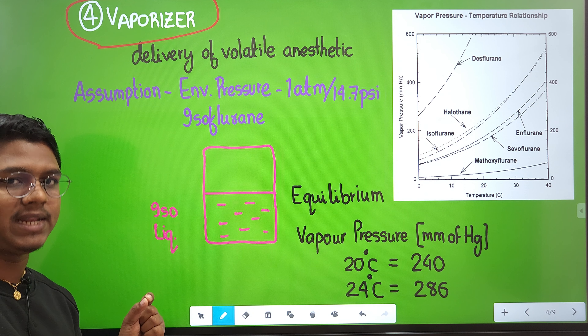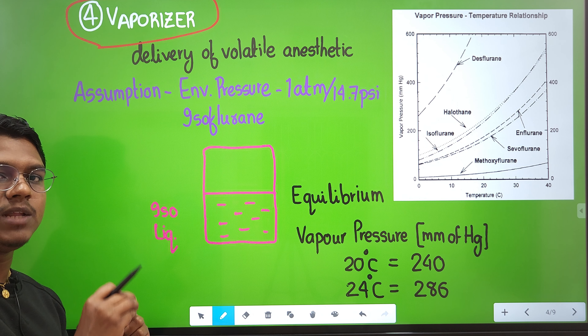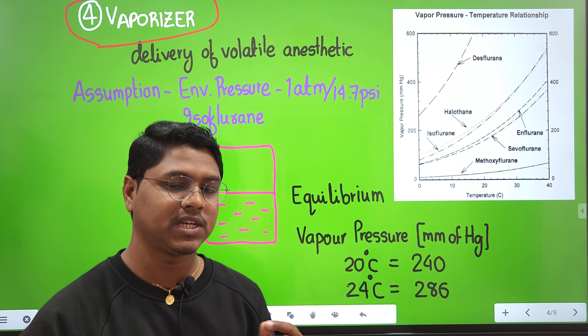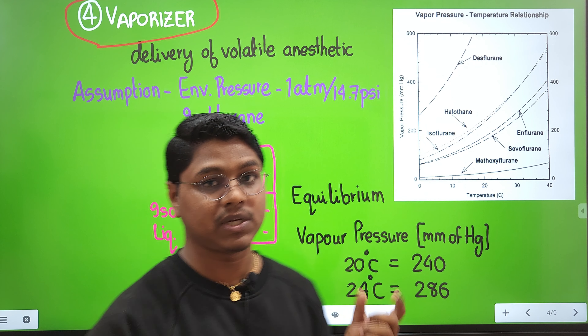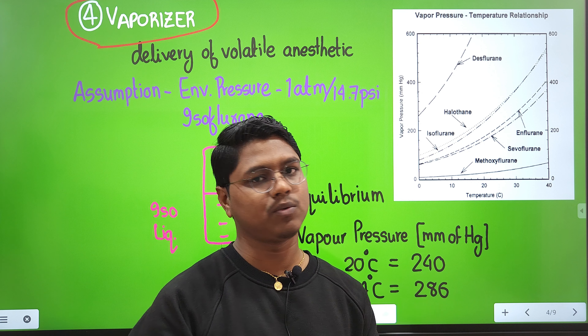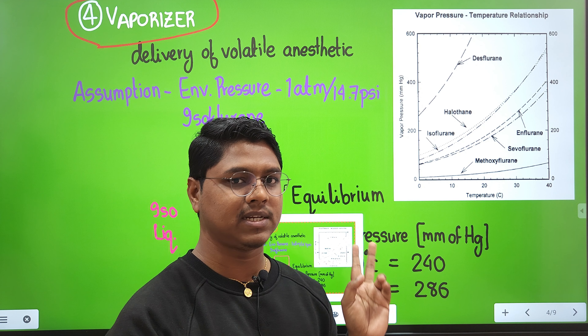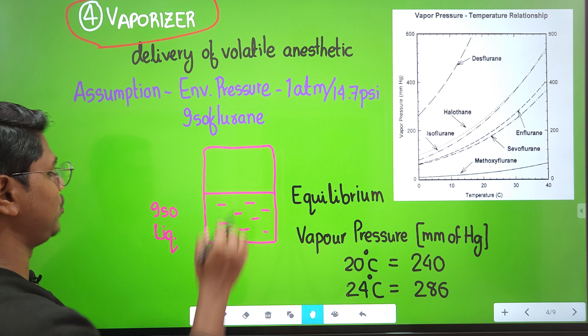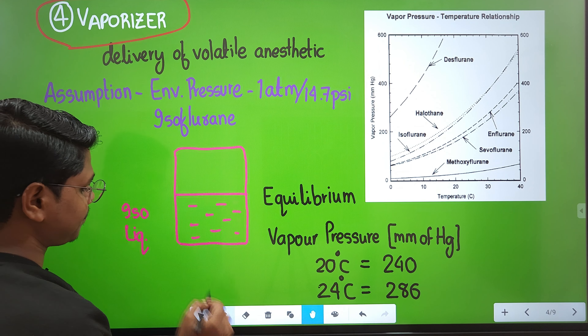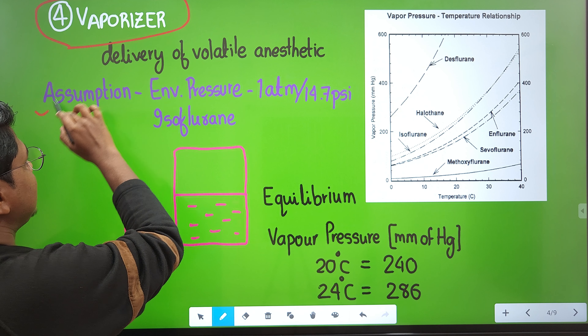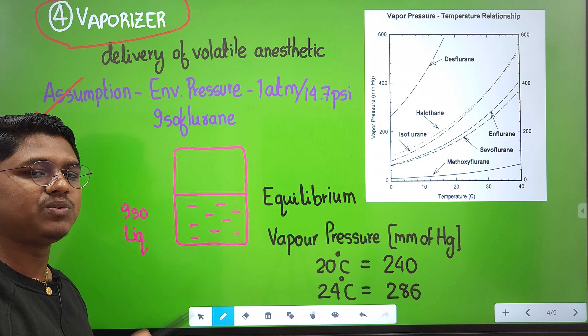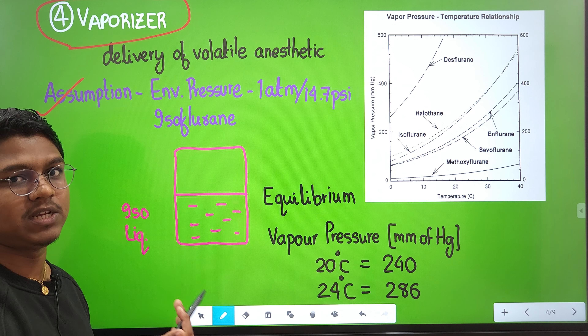The next and most important part is the vaporizer. The vaporizer is used for volatile anesthetics so they can be delivered into the breathing circuit and into the patient. For gaseous anesthetics like nitrous oxide, you do not need a vaporizer because it is already a gas and can be supplied along with oxygen. But for volatile anesthetics, a special instrument — the vaporizer — is required.